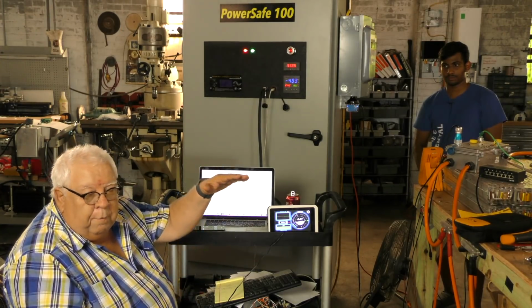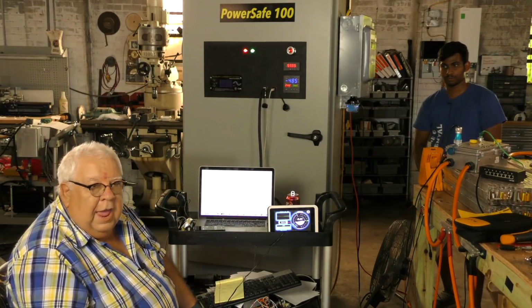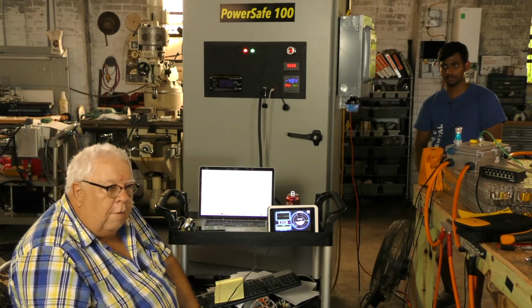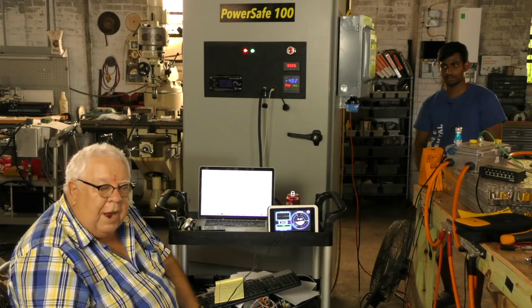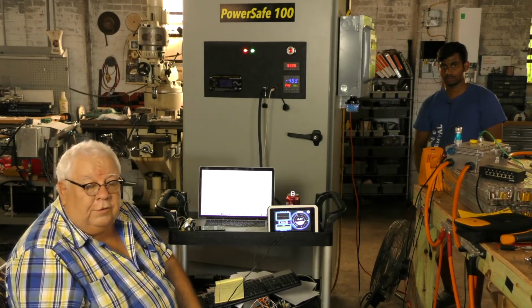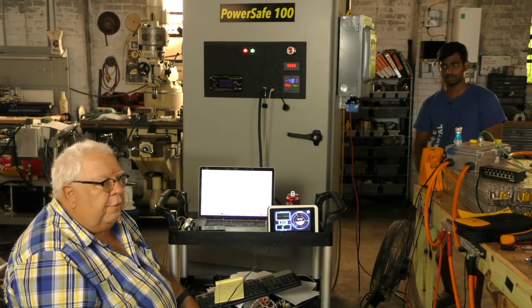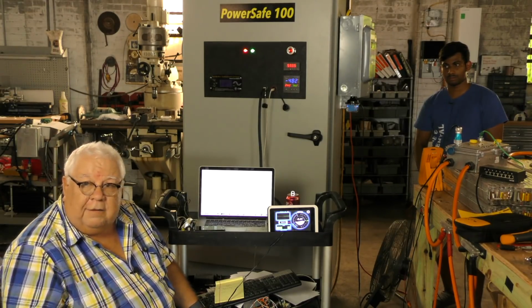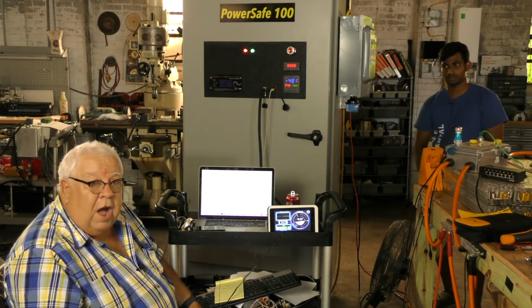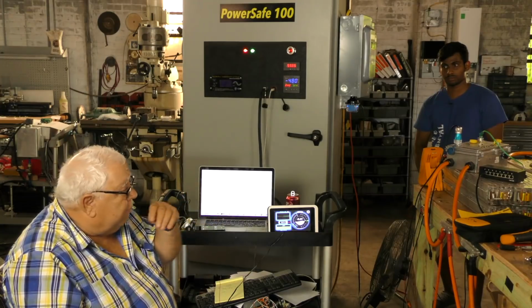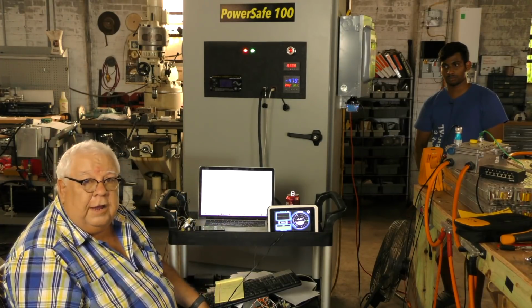We can then make power out of the batteries, off the batteries, make power until we get down to our resume voltage, which we'll set at 3.9 or something, at which point it will close the contactor, and it takes 5 minutes and 12 seconds for the ENphase to come back up and start charging again.